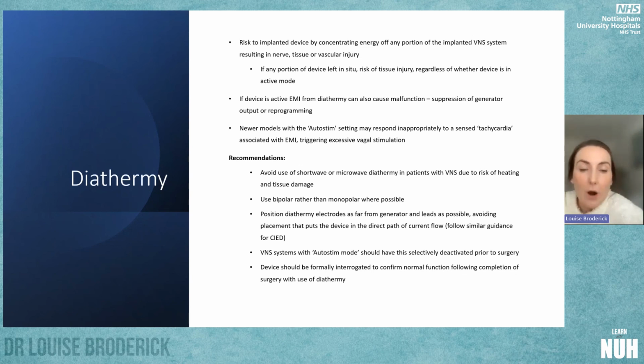So our recommendations, based on the manufacturer's guidelines and the physician's manual, are to avoid the use of shortwave or microwave diathermy to reduce the risk of heating and tissue damage. Use bipolar rather than monopolar diathermy if possible. Similar to guidance for cardiac implantable devices, position the diathermy electrodes as far from the generator and leads as possible, aiming to avoid placement that puts the device in the direct path of the current.